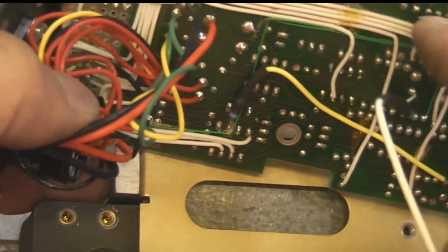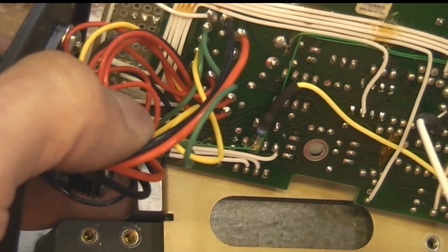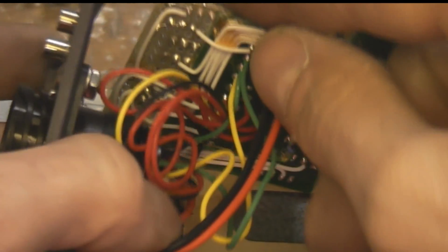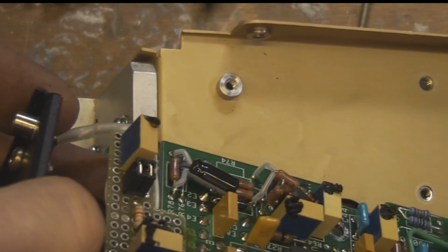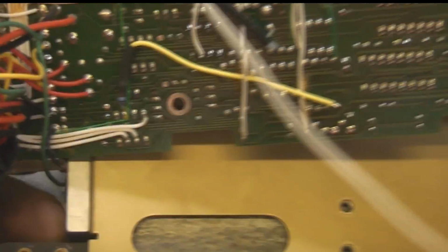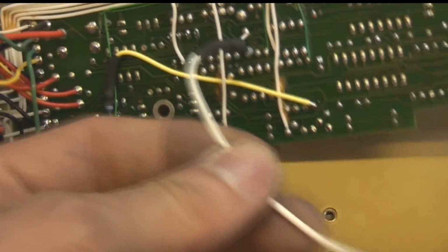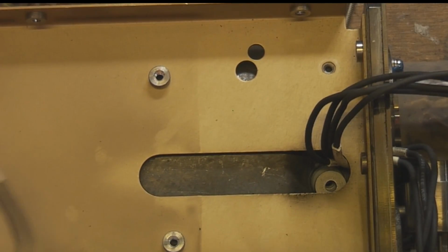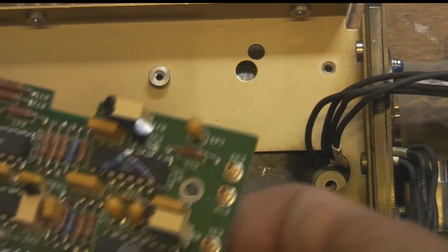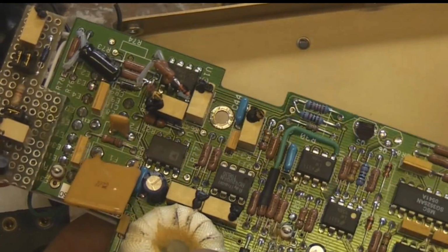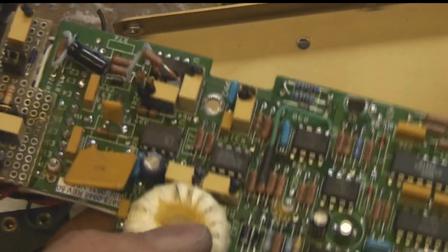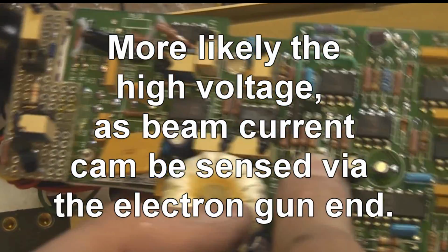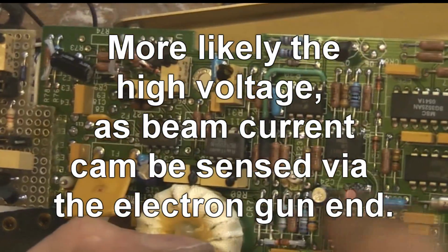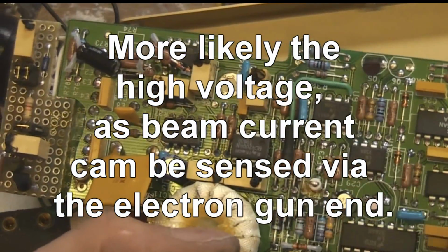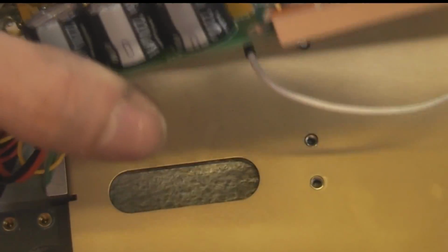I suspect this is possibly not quite so much a bodge wire, but I'd imagine that a lot of these things are customised for different users, so it may well be more of a customisation to a particular requirement rather than necessarily a bodge to fix design errors, but obviously there's no real way of knowing. There's this coax on the back. This feels like it's Teflon or something, and this was connected down to a tab here, so I would think this is probably for sensing the beam current, which is typically on the order of up to a couple hundred microamps. So there's a test point there as well, so there's probably going to be some precision resistors here, so this is going to be just an amplifier to provide an output to measure the beam current.